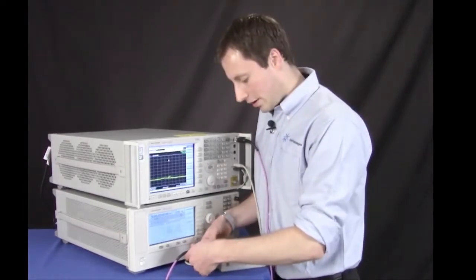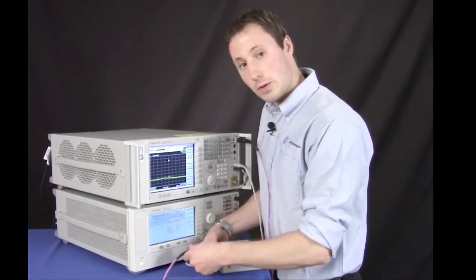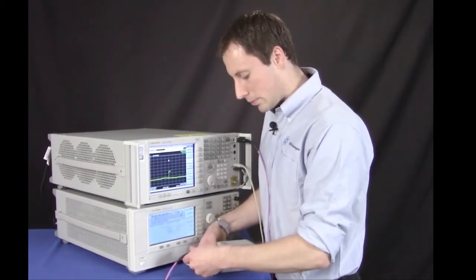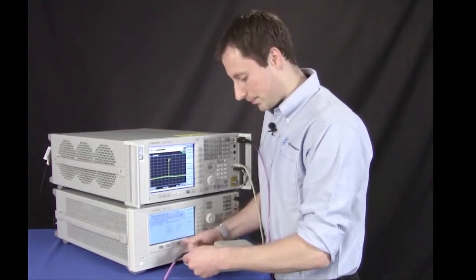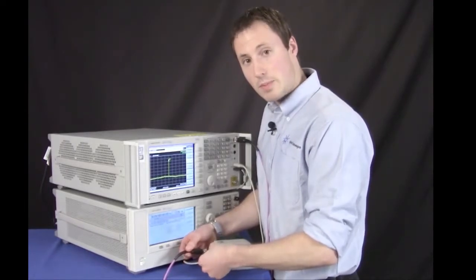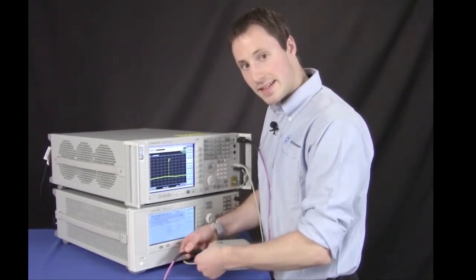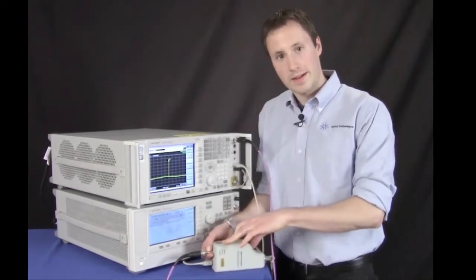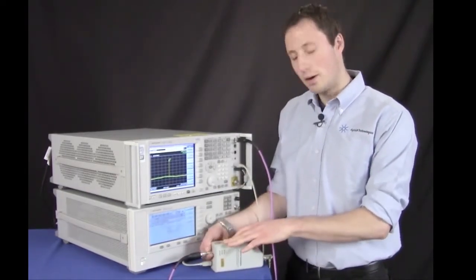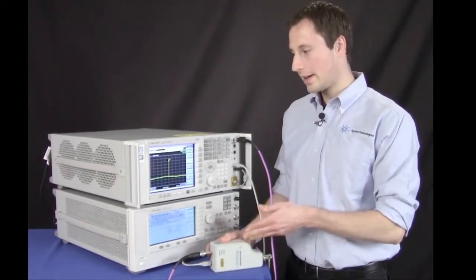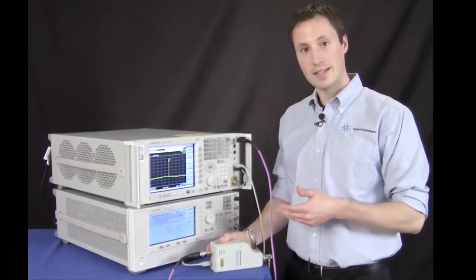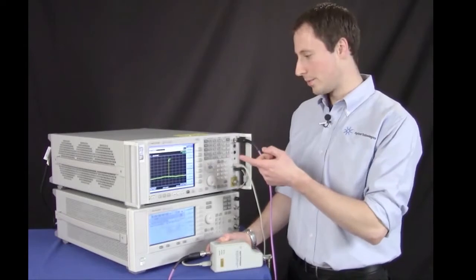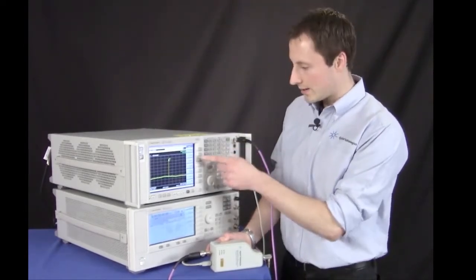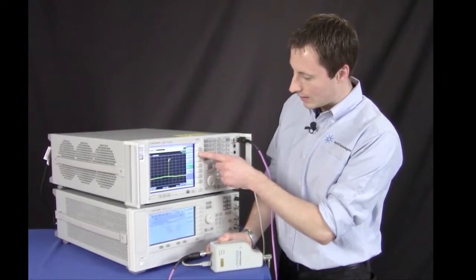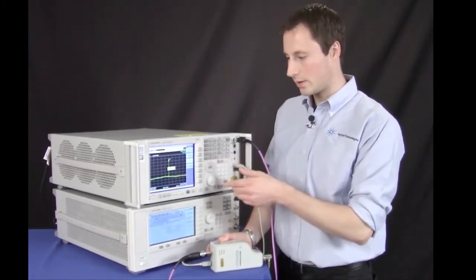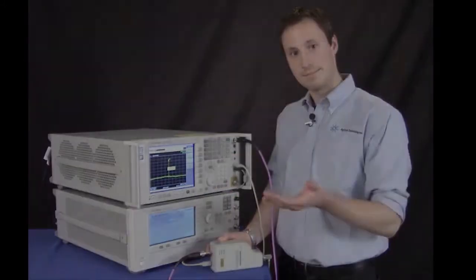One advantage of the Smart Harmonic mixer over legacy mixers is that it has much better conversion loss values. As a result, the Smart Harmonic mixer has better accuracy and sensitivity than the legacy mixers. Now, before I can account for the power loss, I have to realign the external mixer. So to do this, I simply go to our alignments and I just hit external mixer, and now we wait for the mixer to align.